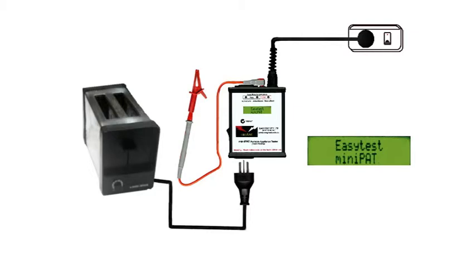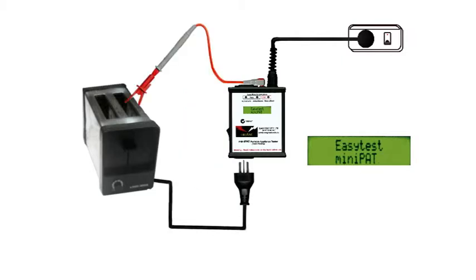The class 1 appliance in this case is a toaster, and it's safer to assume that the appliance may have a fault until we've tested it to prove otherwise. So firmly clamp the earth probe onto any exposed metal we can find, check that the appliance and the miniPAT are both switched off, and plug the toaster into the miniPAT.